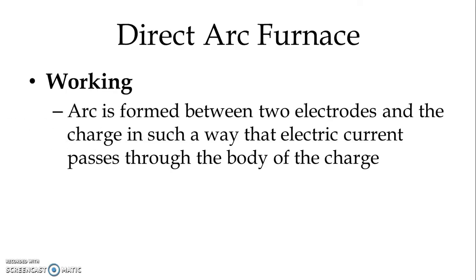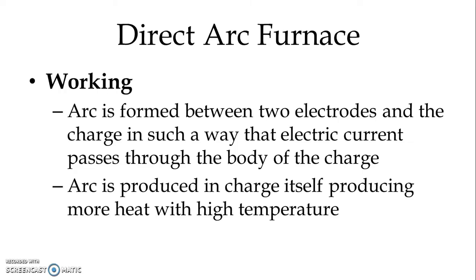Now let us study the working of Direct Arc Furnace. We know that arc must be generated to heat the charge. In case of Direct Arc Furnace, the arc is formed between two electrodes and the charge in such a way that electric current passes through the body of the charge. What we do is short-circuit the electrodes with the charge momentarily. Because of the short circuit, a spark is generated — that is the arc — and the current passes through the charge itself. That is why the name Direct Arc Furnace is given.